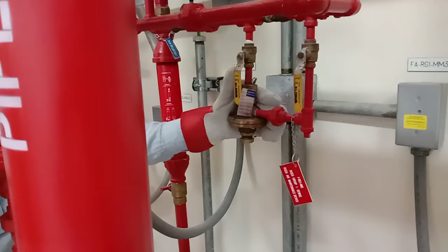Now what is this one? We discussed that regarding dry pilot. This is the dry pilot actuator, right? So one line is connected to the chamber, the differential chamber. From the top side, we have an air connection. Those air connections come all the way from the maintenance device, the air maintenance device, which regulates the flow into the dry pipe valve. We discussed a lot regarding the air maintenance device in the dry pipe risers. It is similar to that, right? So the air will come from this side all the way, and from here it will come to the dry pilot actuators.